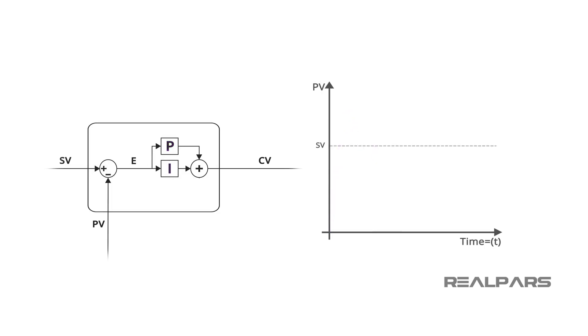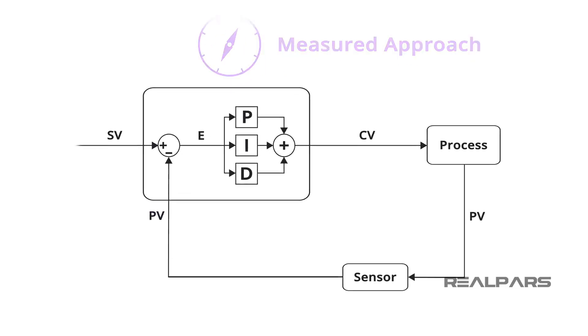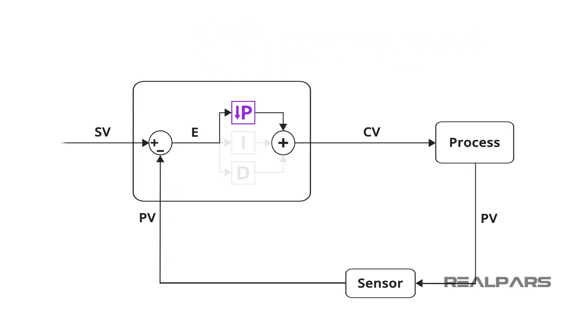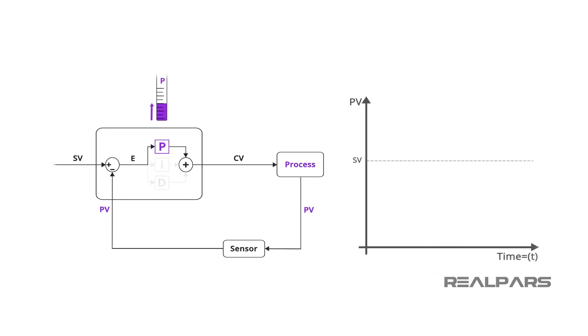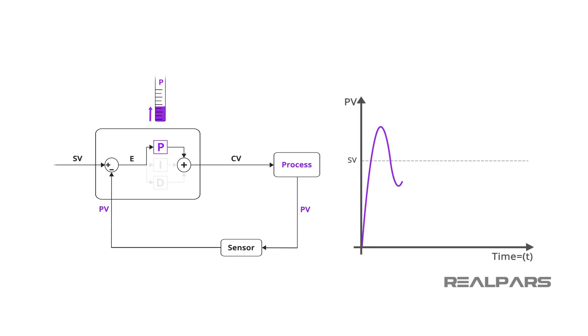Adjust only one parameter at a time and observe the results. Continue in this vein until you have achieved a stable process. A more measured approach is to start with a low gain with integral and derivative disabled. Watch the process and begin incrementally adjusting the gain by doubling the value. When the process begins to oscillate, adjust the gain value down by 50%. Employ a small integral value and watch the process. Double the value incrementally until oscillation occurs, then cut the integral by 50%. At this point, you should be somewhere in the neighborhood and can begin the fine-tuning process.